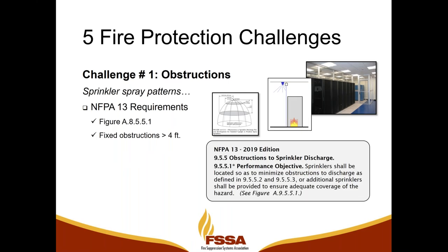For sprinkler spray patterns, understand that if a partition is put too close to a sprinkler, it can impact the spray pattern. So NFPA 13, of course, being the standard for the installation of sprinkler systems, gives us requirements in Chapter 9 for obstructions. And so we need to make sure that those obstructions either don't cause a spray pattern problem, or we need to adjust the location of the sprinklers. And I would suggest that we'd be more willing to adjust the sprinkler location than to tell the data center operator that they can't have a partition to provide proper cooling for their equipment.